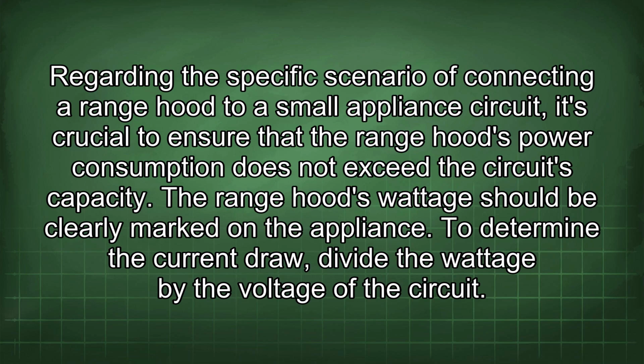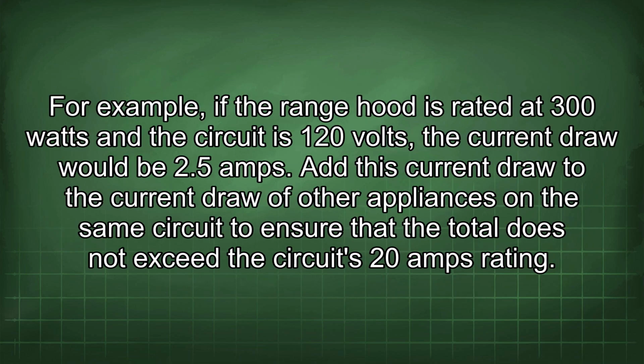Regarding the specific scenario of connecting a range hood to a small appliance circuit, it's crucial to ensure that the range hood's power consumption does not exceed the circuit's capacity. The range hood's wattage should be clearly marked on the appliance. To determine the current draw, divide the wattage by the voltage of the circuit. For example, if the range hood is rated at 300 watts and the circuit is 120 volts, the current draw would be 2.5 amps. Add this current draw to the current draw of other appliances on the same circuit to ensure that the total does not exceed the circuit's 20 amp rating.